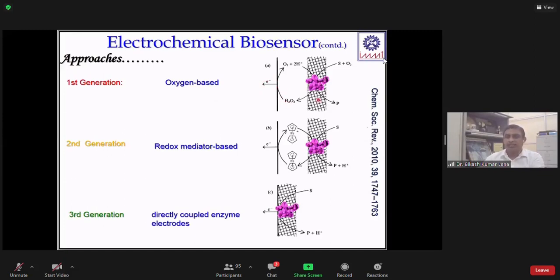So this is the first generation they developed, but here the problem was they used the enzyme inside the solution. So the enzyme activity takes place inside the solution, generating hydrogen peroxide, but the electrode is far away from the solution, and slowly the hydrogen peroxide generated diffuses to the electrode surface. That's why there is a delay in the passage of signals, so this first generation was not that much sensitive, and we cannot get a low limit of detection, because not all of the hydrogen peroxide generated reaches the electrode surface—some gets dissolved inside the electrolyte.